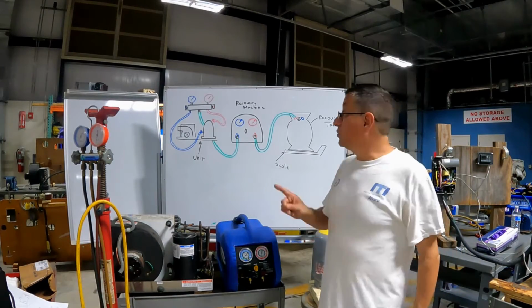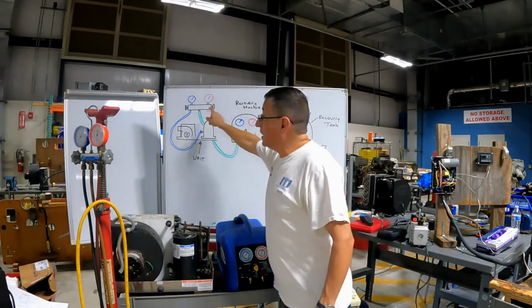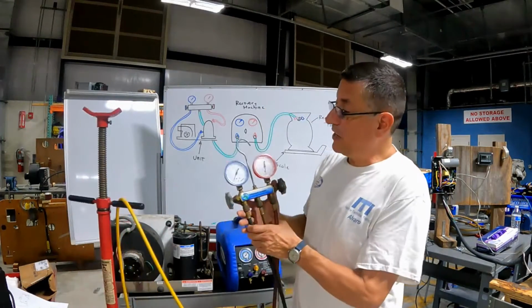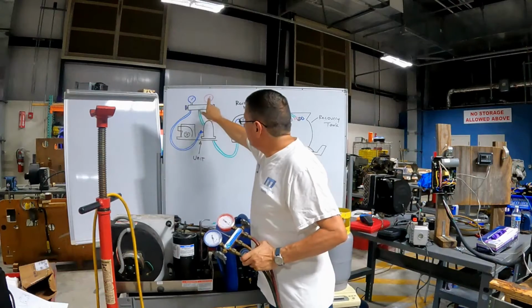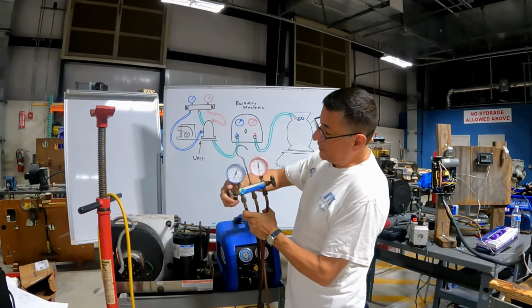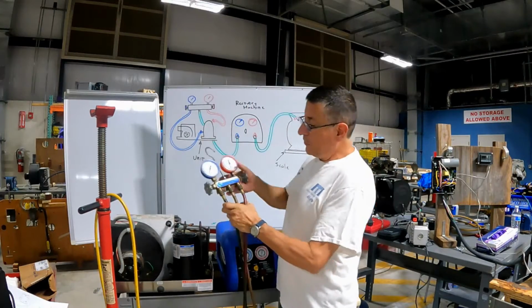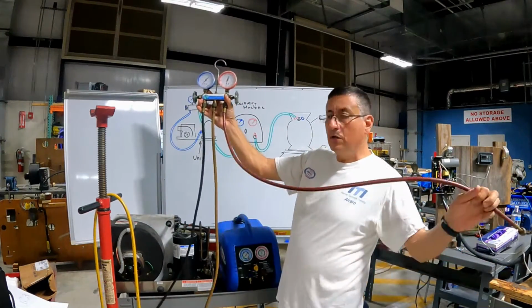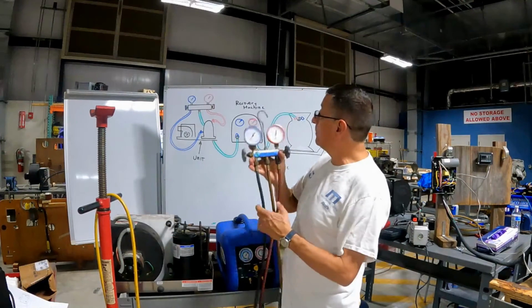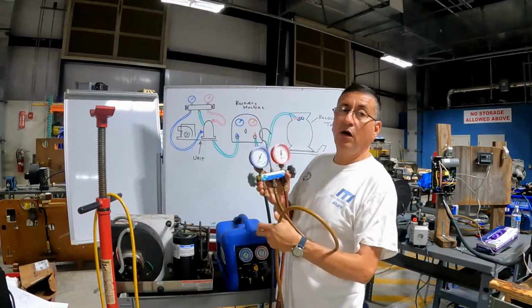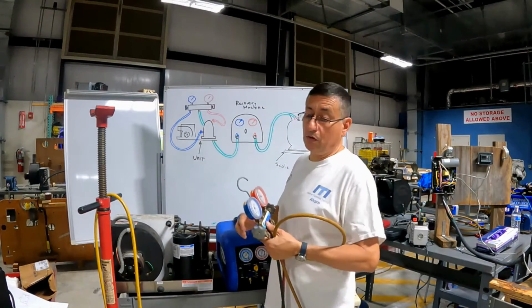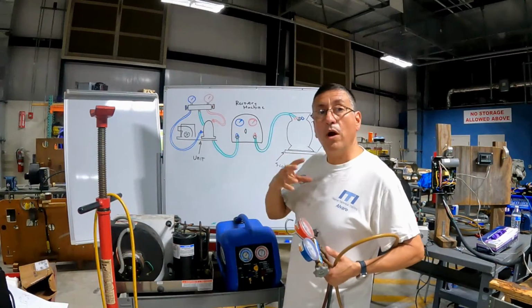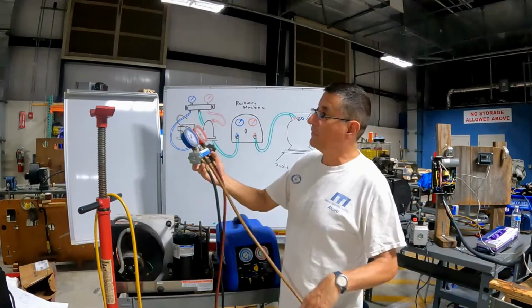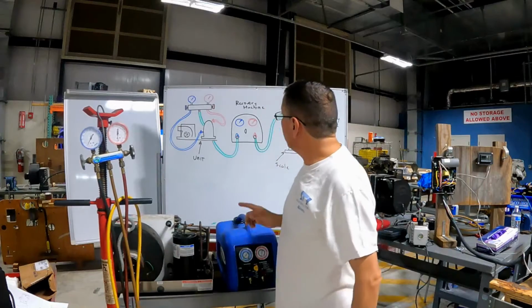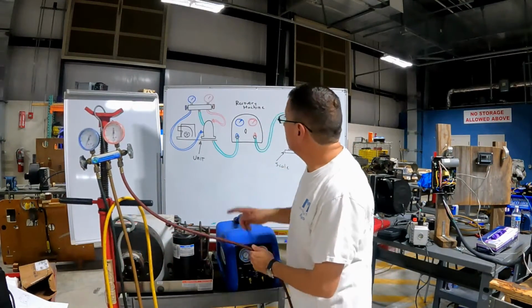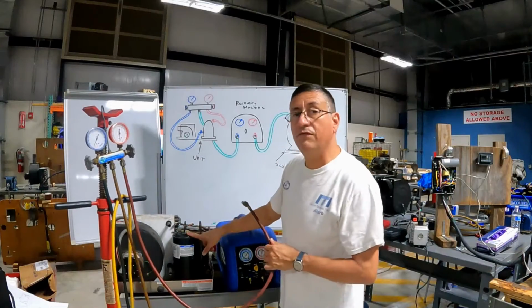The first step, we are going to do this connection. Look at this. This is the set of gauges. Remember that in the set of gauges we have the low pressure and high pressure gauge. We have the valve for high pressure. We have the valve for low pressure. We have one hose, the red hose for high pressure, and we have the blue hose for low pressure, and we have the yellow hose to transfer, the middle one. I use green because yellow is not good for the whiteboard. Okay, this is the set of gauges. I'm going to locate the set of gauges over there, and we are going to connect the set of gauges in this way. The red, the high pressure, into the high pressure side of the compressor.